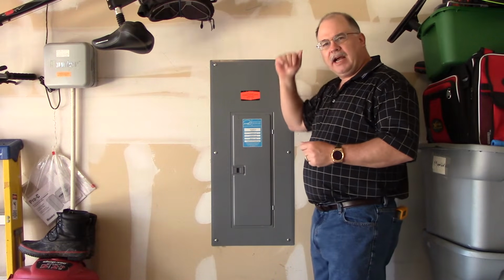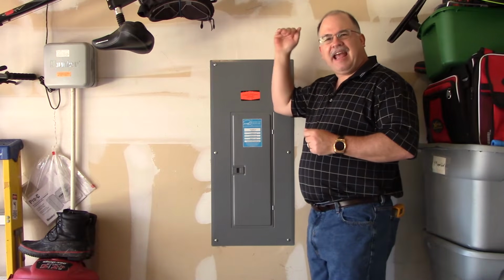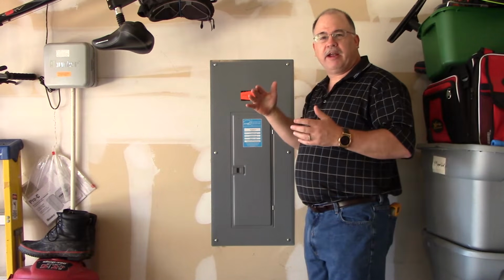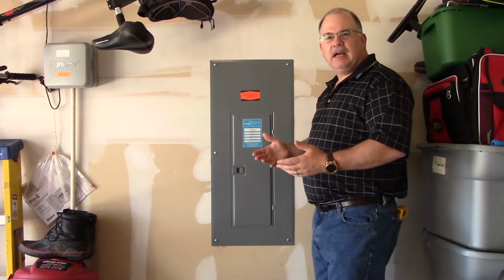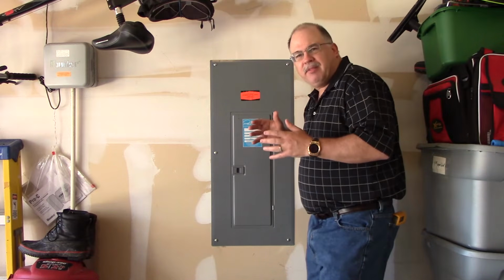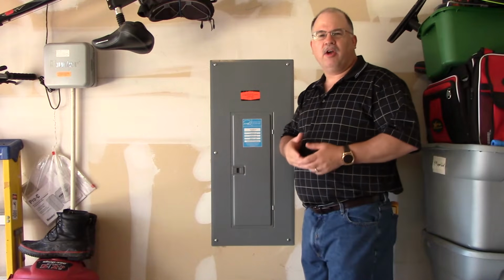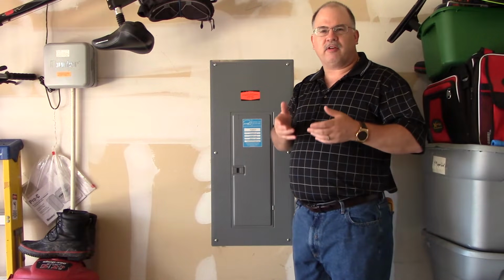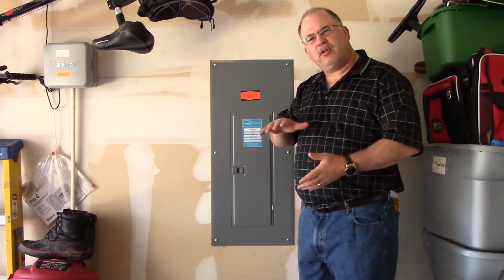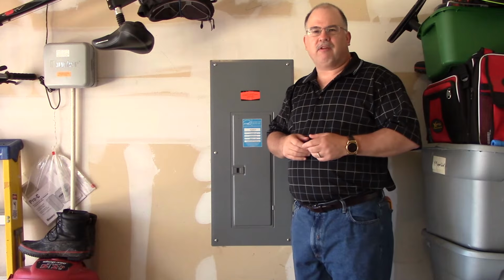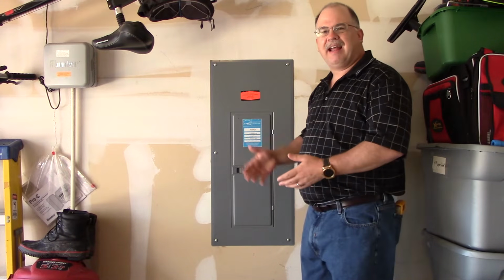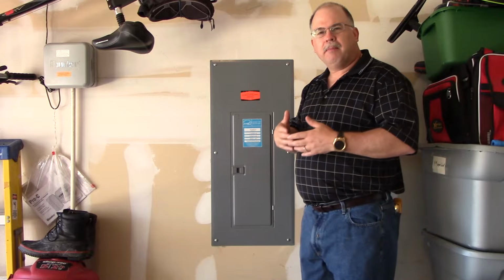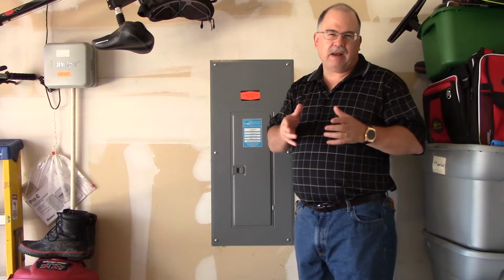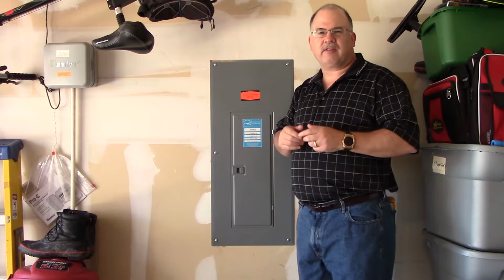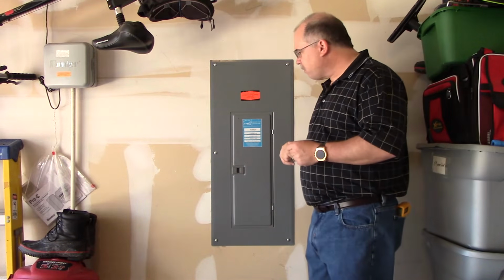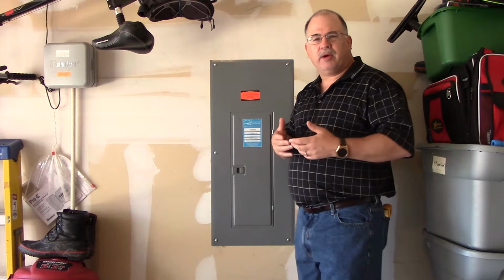Now, what about the working height? We want to make sure it's at least 6.5 feet or to the height of the equipment, whichever is greater, that we want to maintain that clearance here so that you can actually get in here without ducking down and doing anything like that. Now, there are some exceptions for existing dwellings that have services that are 200 amps or less. Then you can have some reduced clearances, and that's something that you might run into as a home inspector on an older home that's not going to have the adequate height that you had for new codes. But you have to look at that, and that's something that you might want to look at in 110.26. There's an exception for that reduction of clearance. But right now we're looking at it from a municipal standpoint and a home inspector on a home.